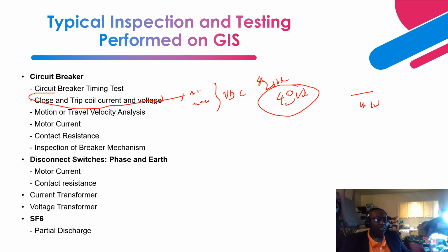Next is the motion travel analysis. Motion travel analysis testing is performed for the breaker mechanism and also for the contacts. It is basically a slow motion analysis to find how the contacts are operating, so it is more of a velocity measurement. The velocity is determined and compared with the factory acceptance testing or the manufacturer's recommendation. Then also the motor current.